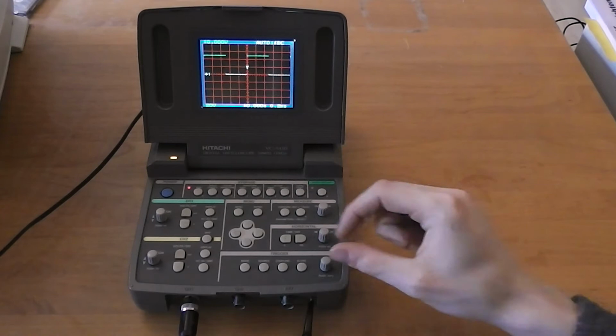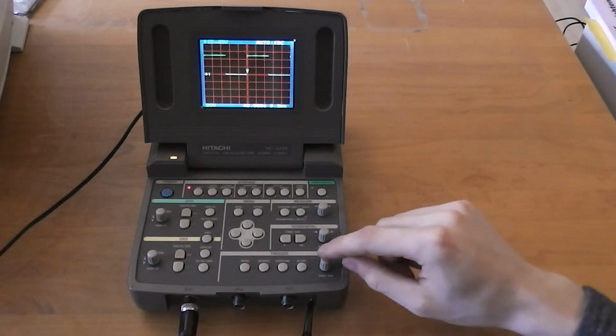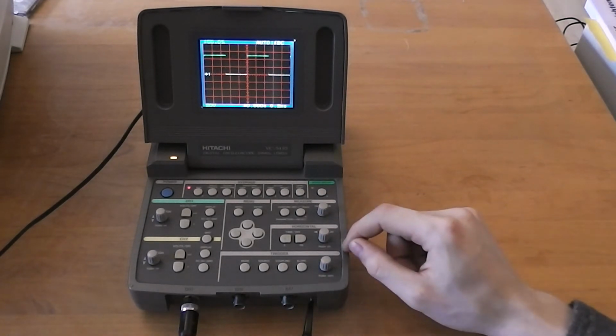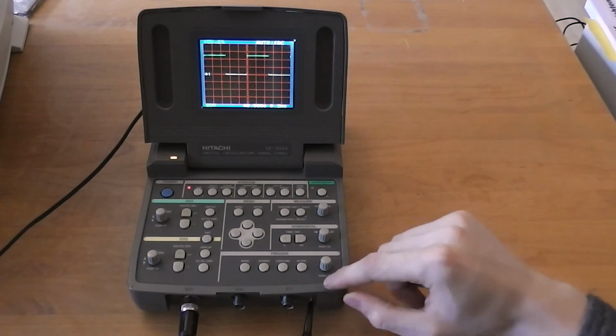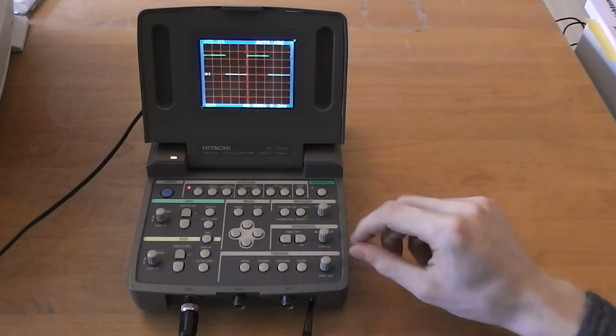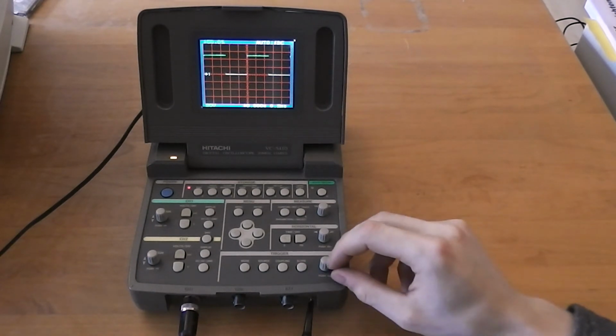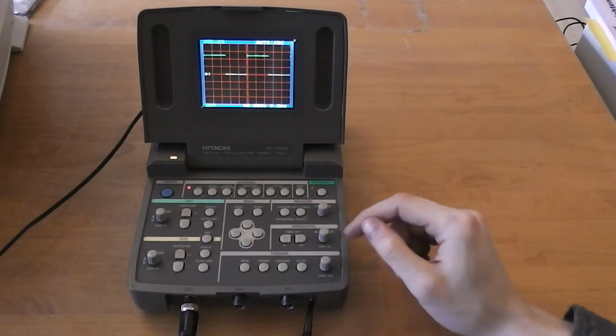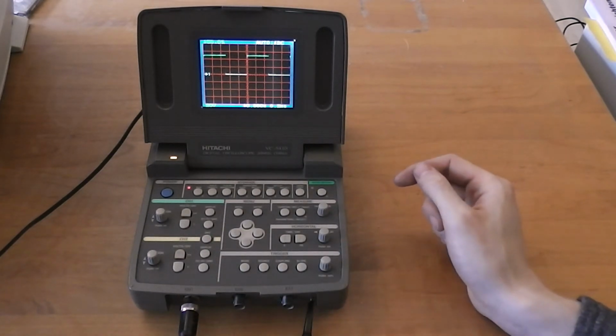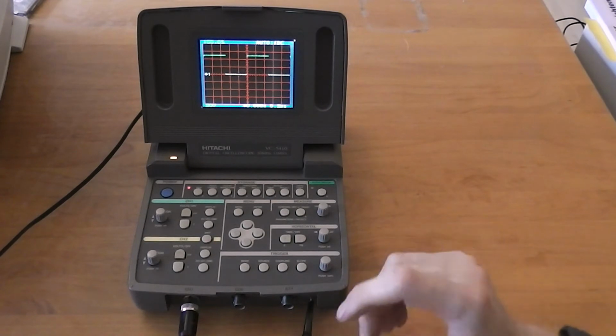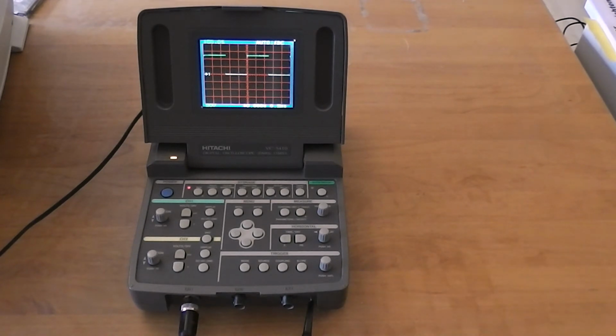What I kind of like, you can push all these also for the trigger level. Just push on these and they will be reset to the default position, so 50% trigger level, and these are 0 volts. And it does have all the settings that you expect from a standard oscilloscope.